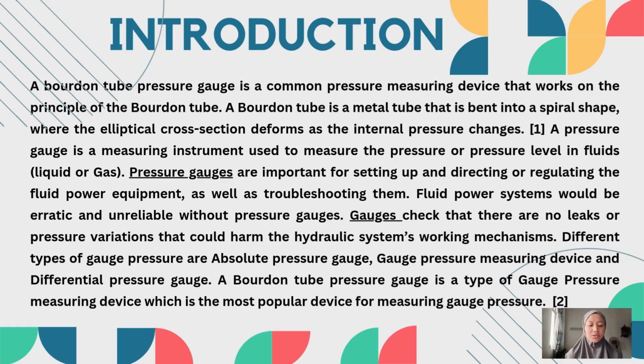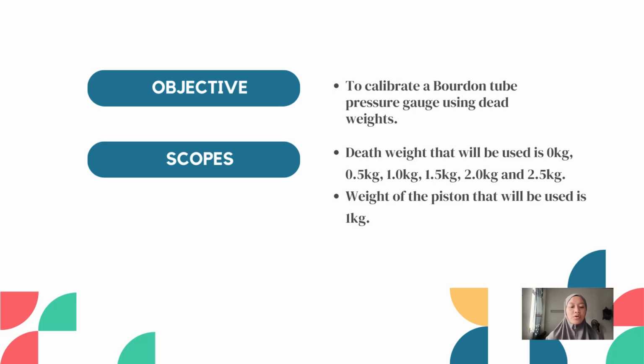Different types of pressure gauges are the absolute pressure gauge, the gauge pressure measuring device, and the differential pressure gauge. A Bourdon tube pressure gauge is a type of gauge pressure measuring device, which is the most popular device for measuring gauge pressure. This is our objective.